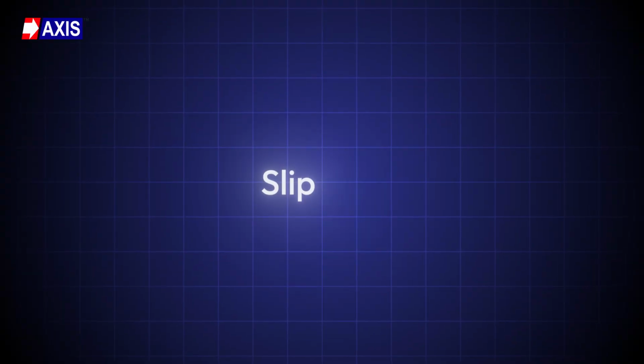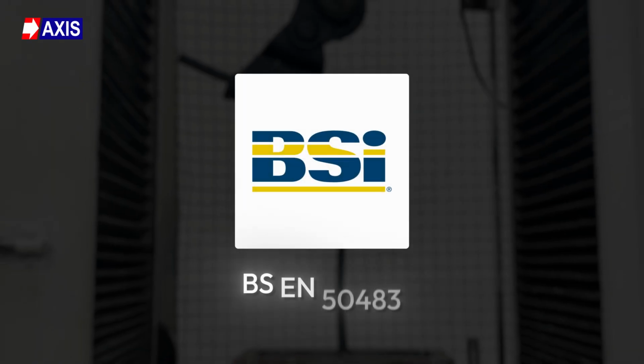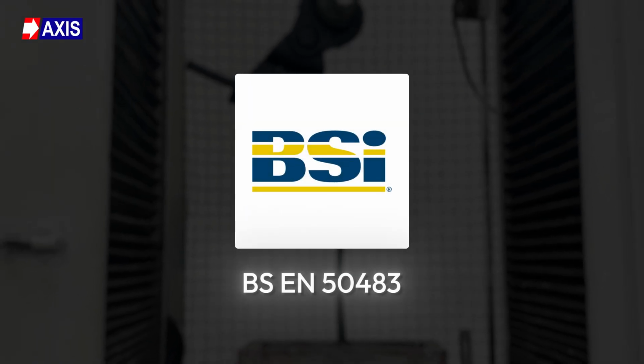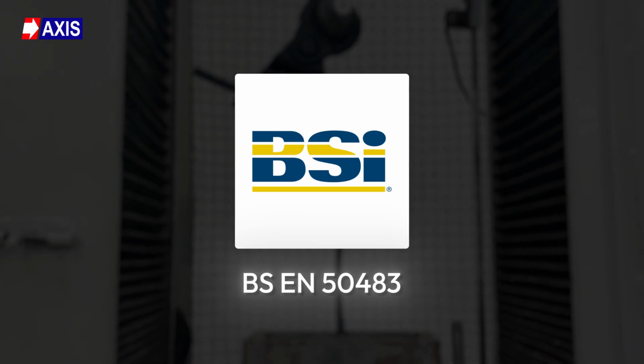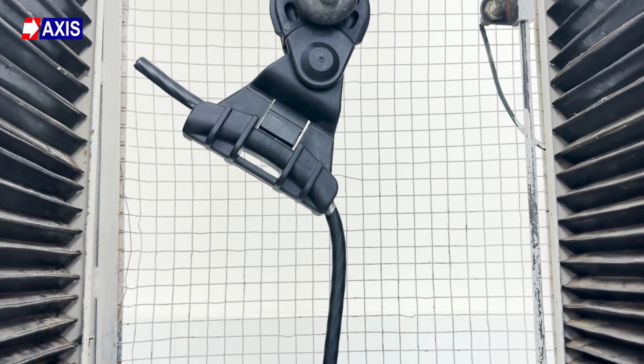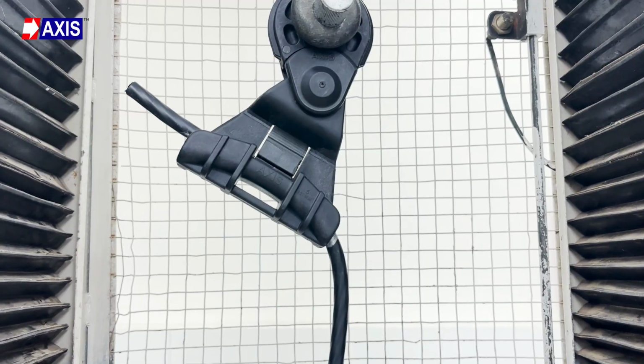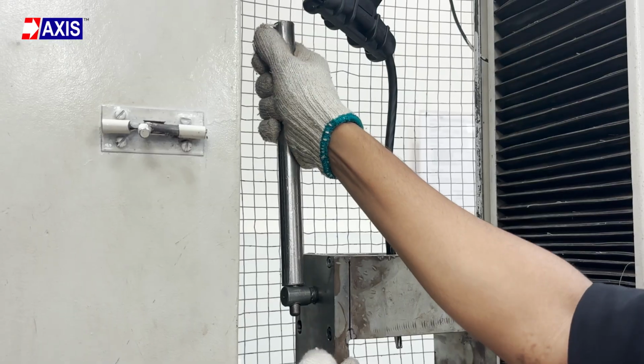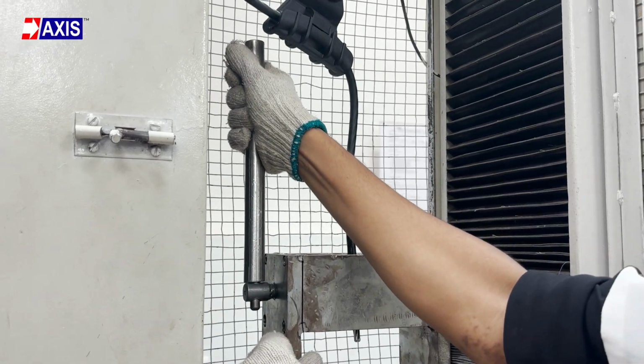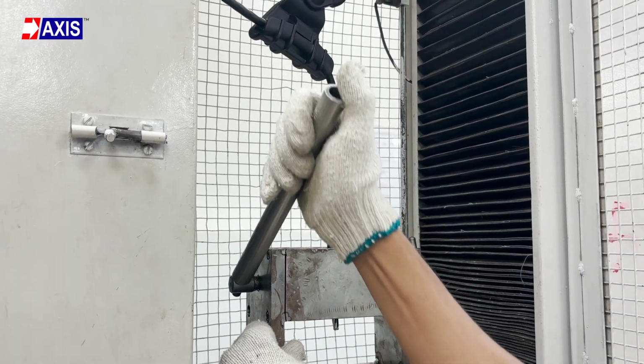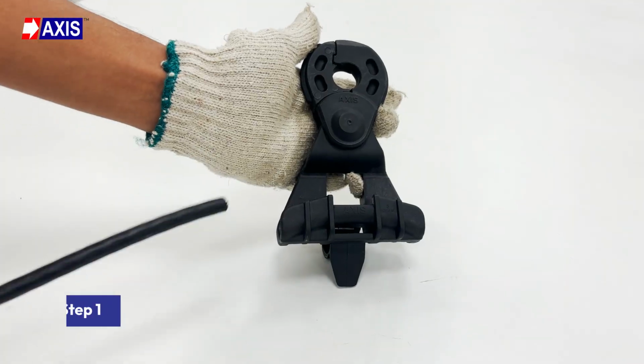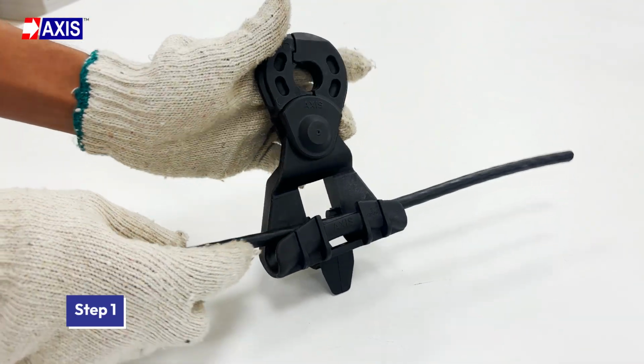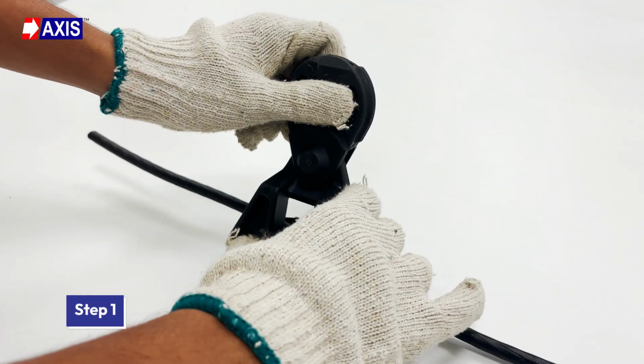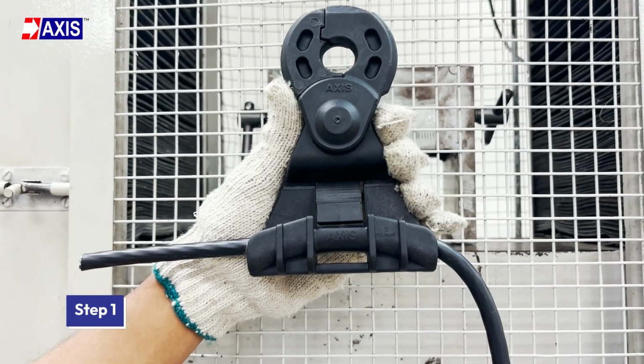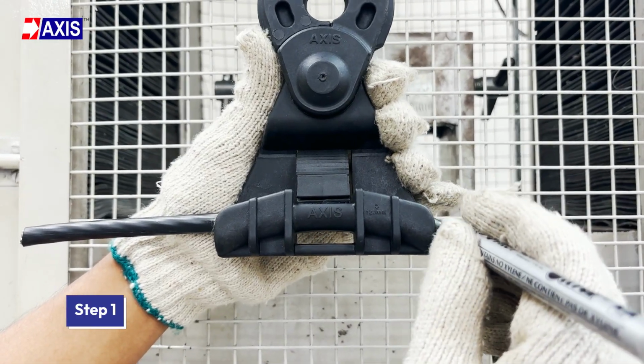Next, slip test as per BS EN 50483-3. This test verifies that your suspension clamp can securely hold the neutral messenger without allowing it to slip when it is subjected to mechanical load at normal ambient temperature. Step 1. Mount the suspension clamp on a section of insulated neutral messenger cable. Mark the messenger at the point at which it leaves the clamp.